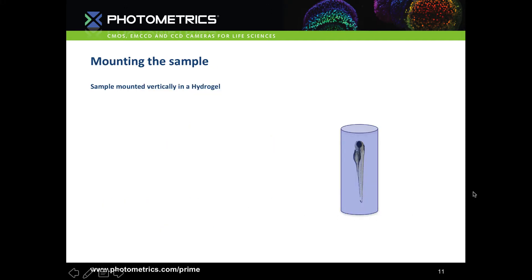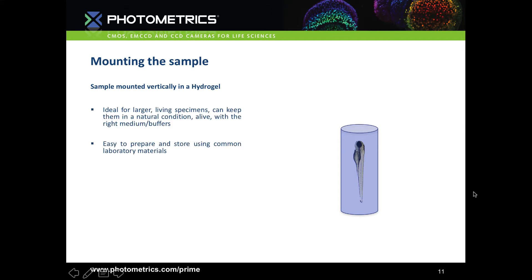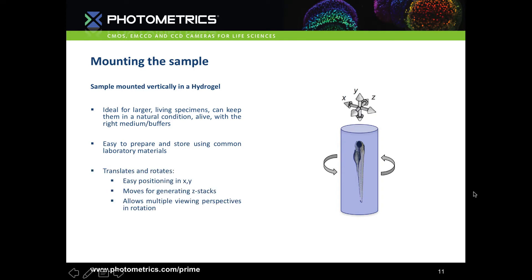Next we want to look at how we mount the sample to take full advantage of the lightsheet. The most common way is to mount the sample vertically in a hydrogel. It's ideal for larger living specimens because you can keep them in natural conditions with the right medium and buffers. It also translates and rotates really nicely — easy positioning in X and Y, then you move it through the lightsheet to generate Z-stacks and rotate for multiple viewing positions.